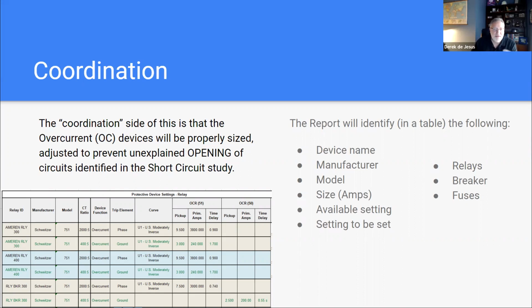Yeah, this comes up quite a bit, especially since we do a lot of healthcare design. What's odd in the NEC is Article 517 applies to healthcare, and it specifically allows for a lack of coordination below 0.1 second in 517.32, I think. It's weird, but if you have a project not subject to 517, you're bound to the requirements, I think in section 700 or 701, where you have to have a fully coordinated system, which means you can't have any lack of coordination in that region.